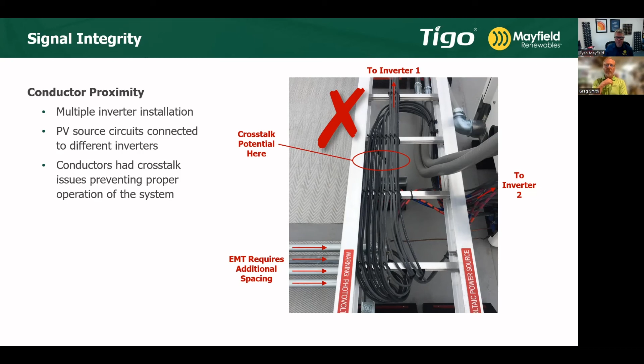All of these things are true. There's so much that can happen when you have some type of intermittent signal integrity issue, or crosstalk, or anything in between. The MLPE or whatever you're using may not be able to connect—for ours, the little relay may not shut to allow the voltage to come through. Worst case, it may chatter, opening and closing repeatedly. Those relays aren't made to open and close a billion times a second, and that's going to stress the electronics.